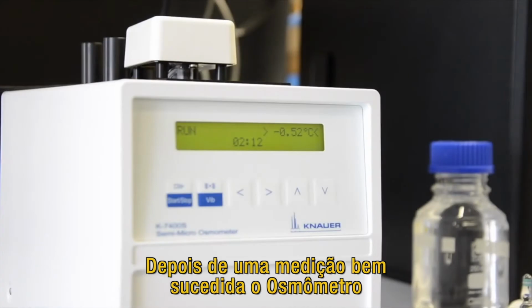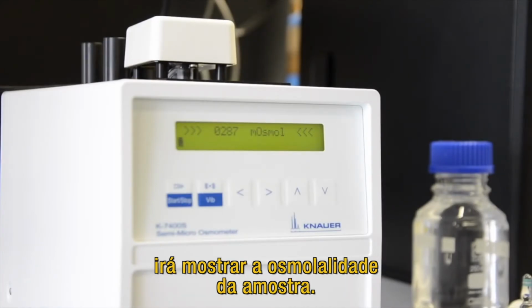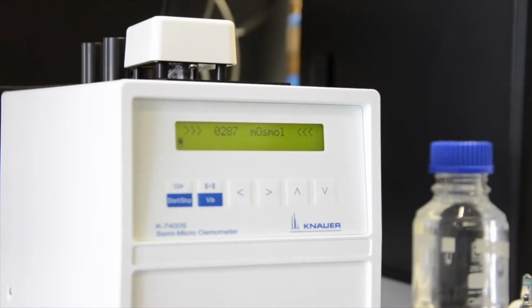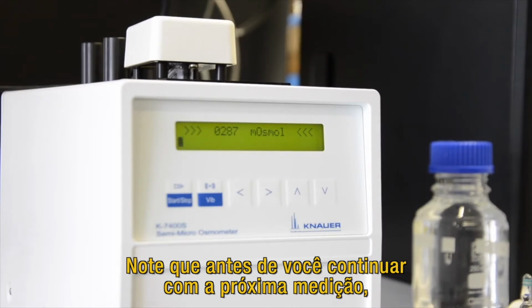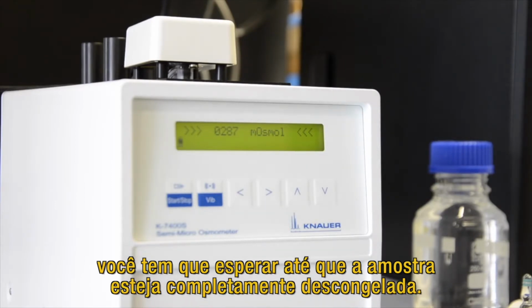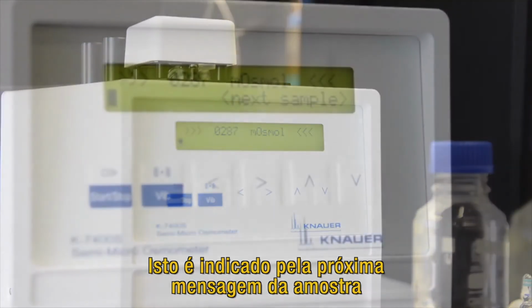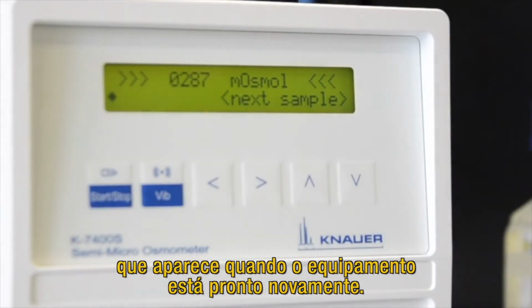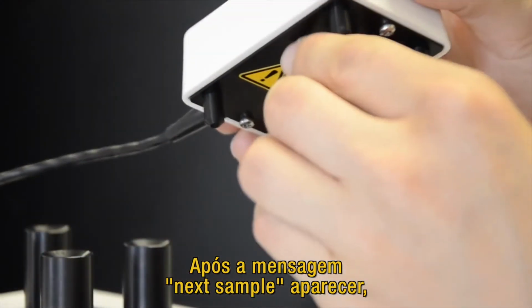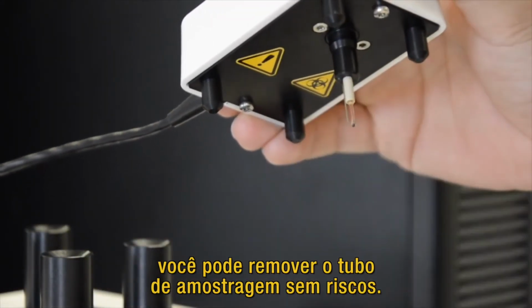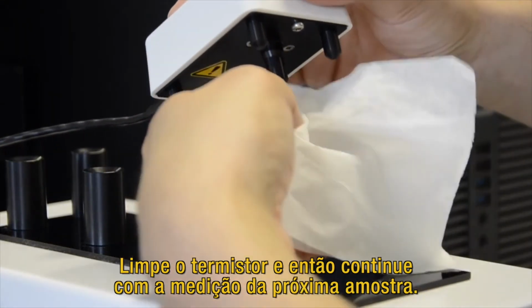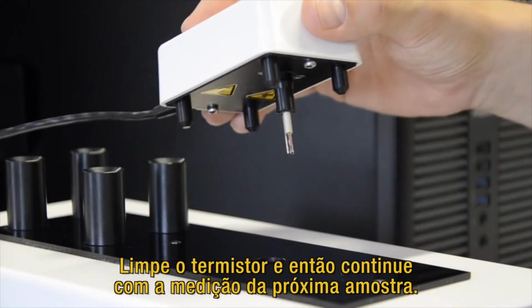After a successful measurement, the osmometer will display the sample's osmolality. Note that before you proceed with the next measurement, you have to wait until the sample is completely thawed. This is indicated by the next sample message that pops up when the device is ready again. After the next sample message is displayed, you can remove the sample tube without any risk, clean the thermistor and then proceed with the next measurement.